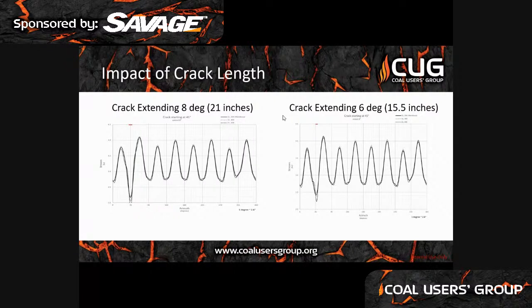What you see here are a couple examples of the modeling results. We started at a 16-degree crack and worked our way down. Shown here is an 8-degree, or about 21-inch long, crack. It shows a very apparent change in the normal pattern, but that's still pretty large, so we kept going smaller. The second graph shows a 6-degree or 15-inch crack, which again is still really apparent. You can see a change in the expected pattern.